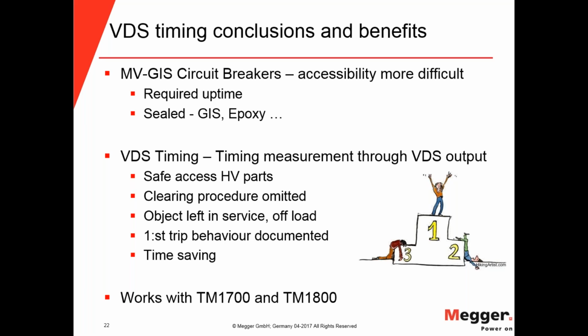And the benefits with the VDS timing then is that you have a safe access to your primary parts through this VDS interface, and the clearing procedure can be omitted.